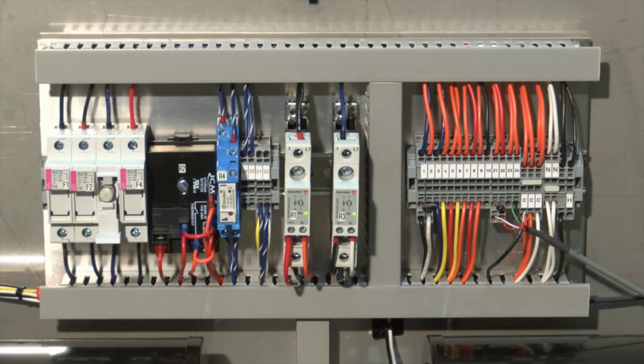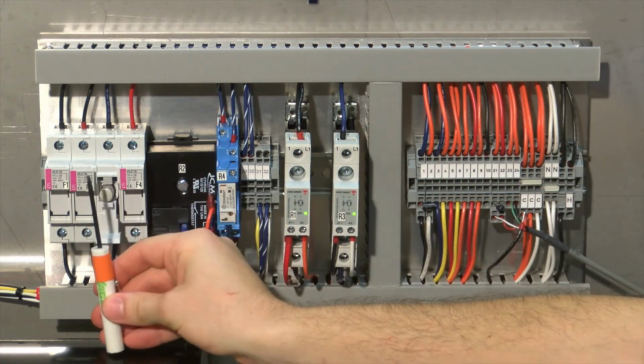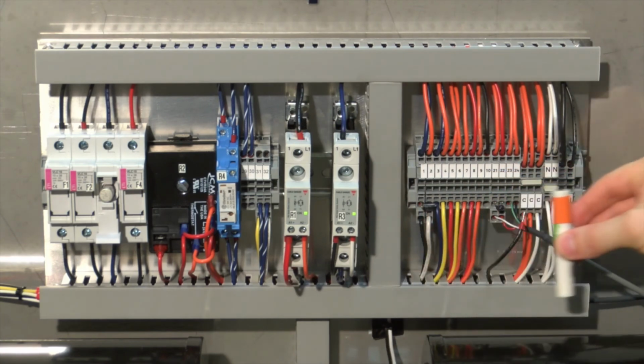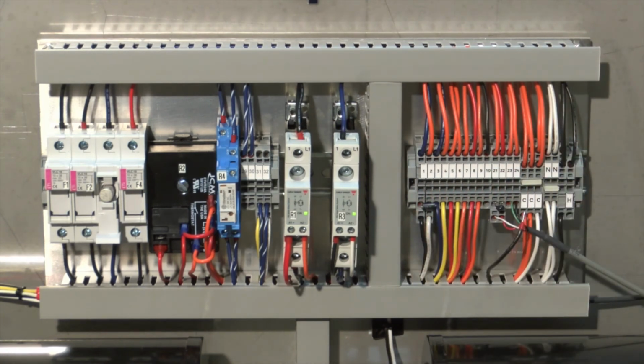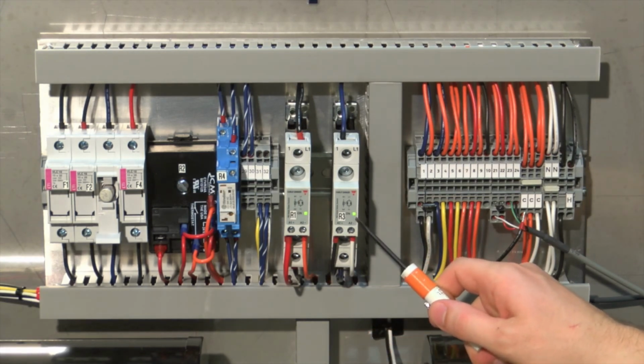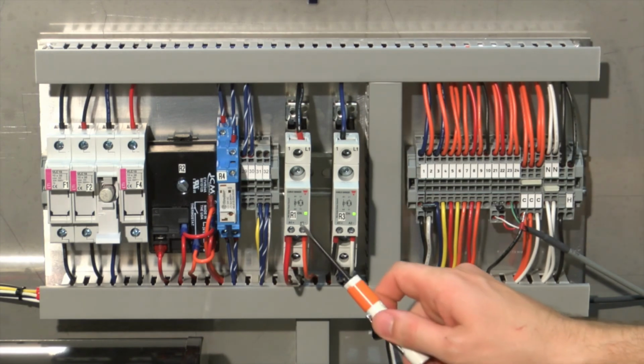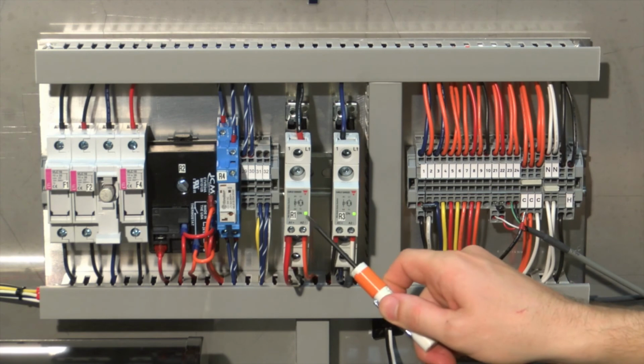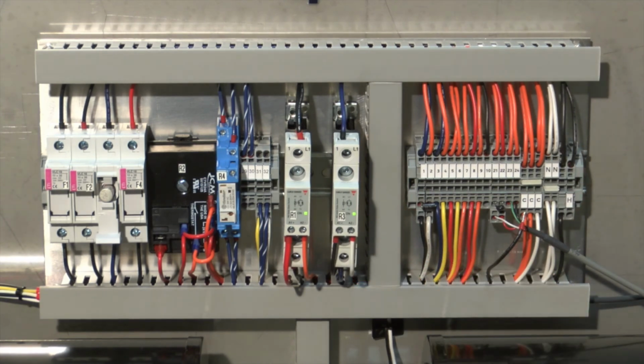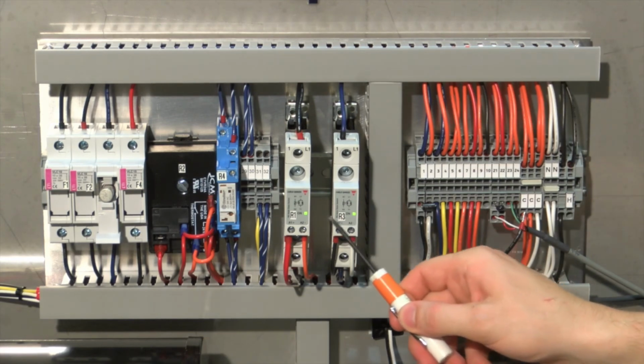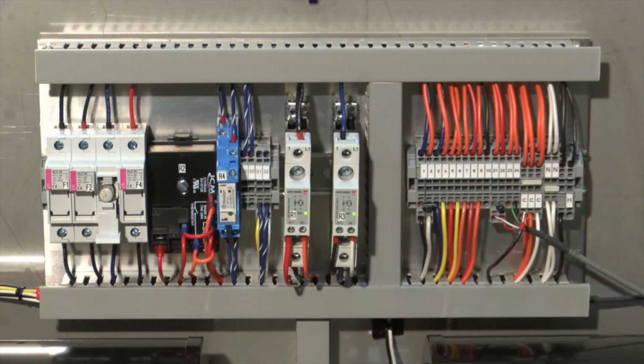A failed or damaged component will also not allow your system to operate correctly. Looking at the MistFree's interface plate, you'll see the fuse block, the R2 relay, the R4, the R1, the R3, and the terminal block to connect the wiring. The transducers are controlled by the R1 and R3 solid-state relay. When the transducers are operating, both these relays should be lit green. If your transducers are not operating, also check these relays to see if they are lit. If one of these is not lit, you can follow your wiring diagram or contact Humidifirst to investigate why.